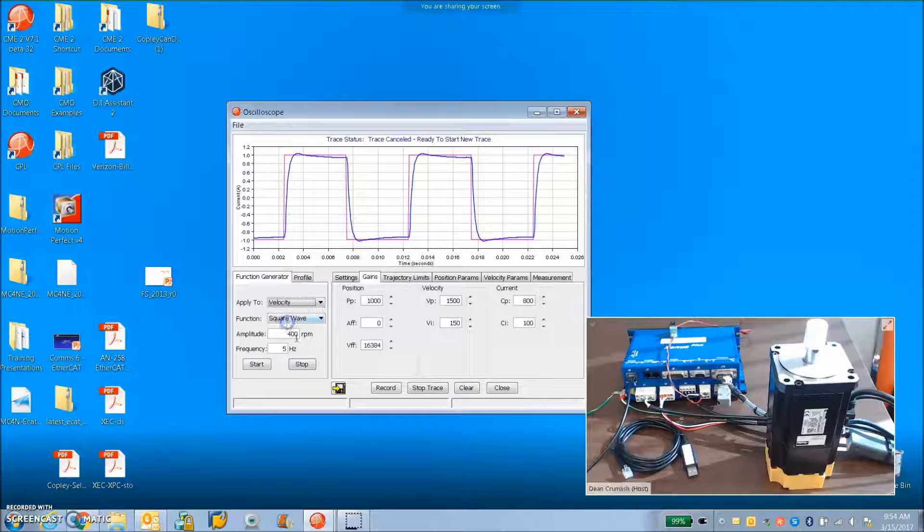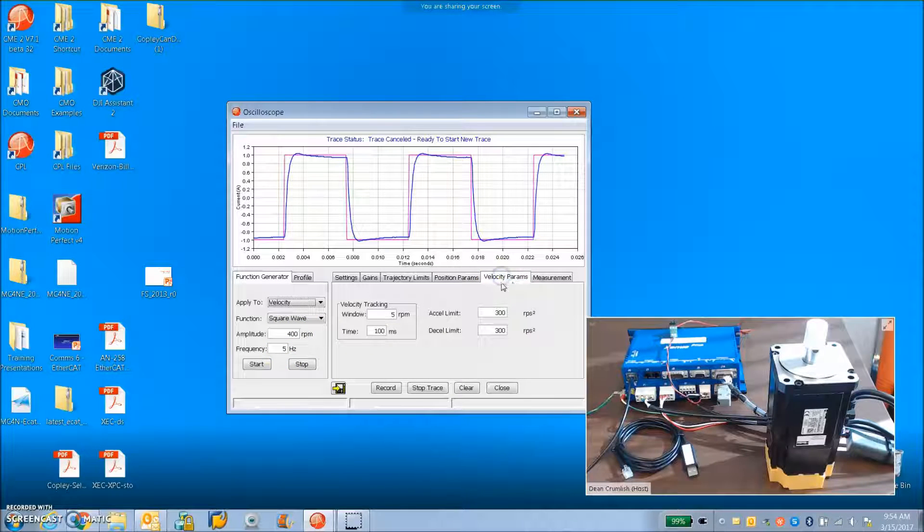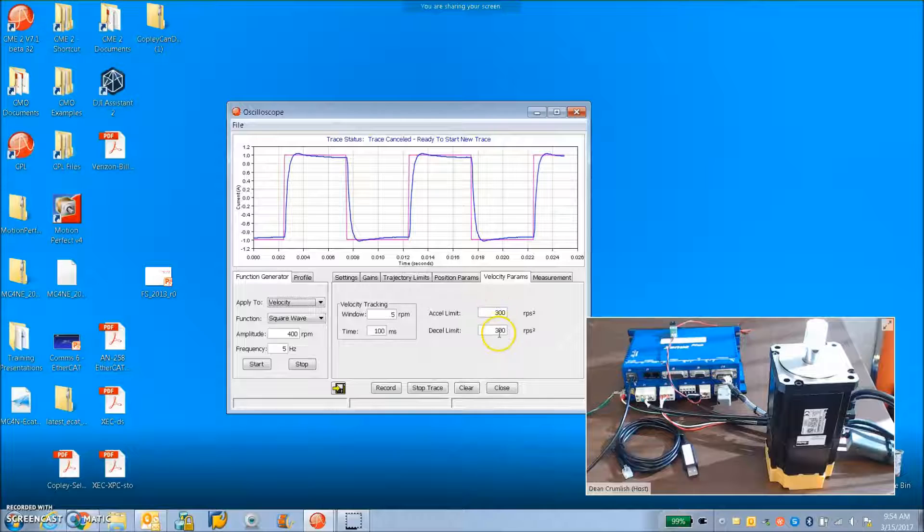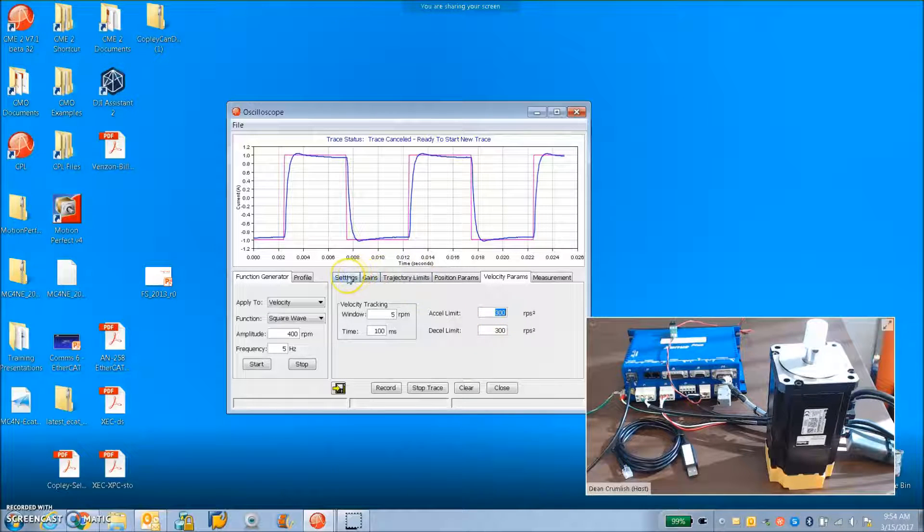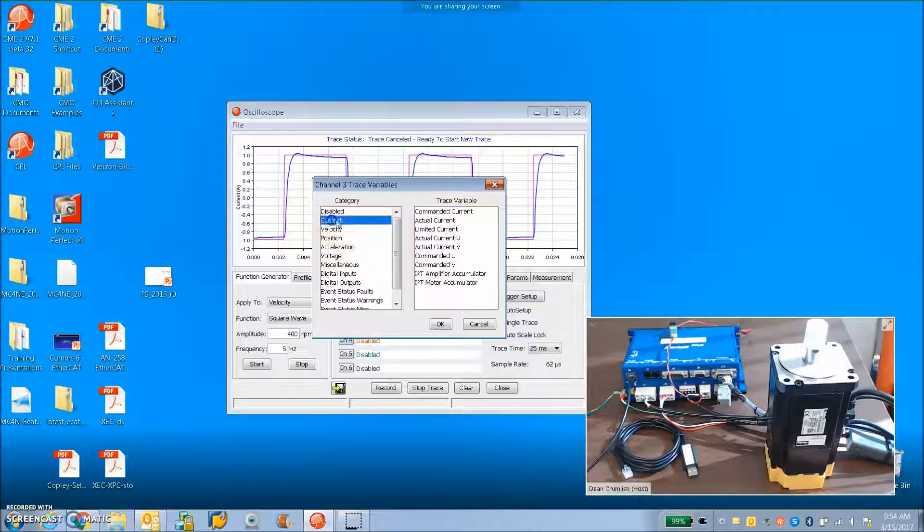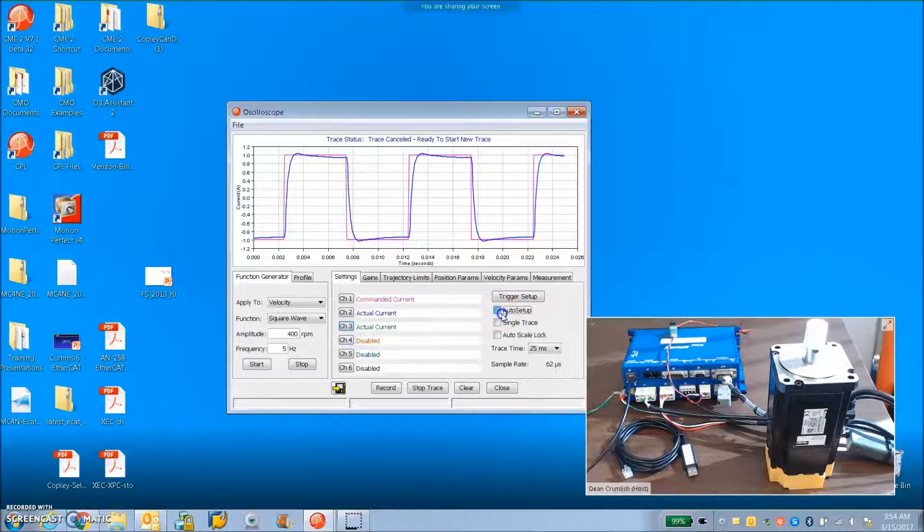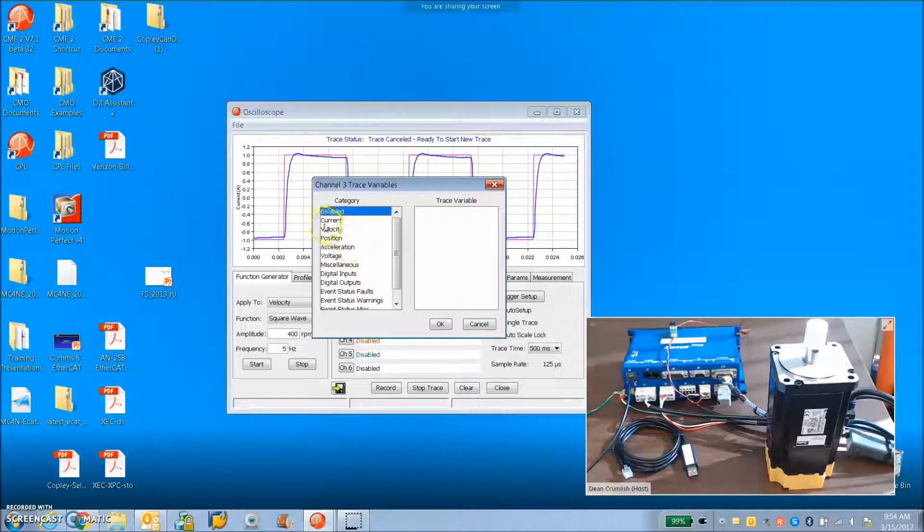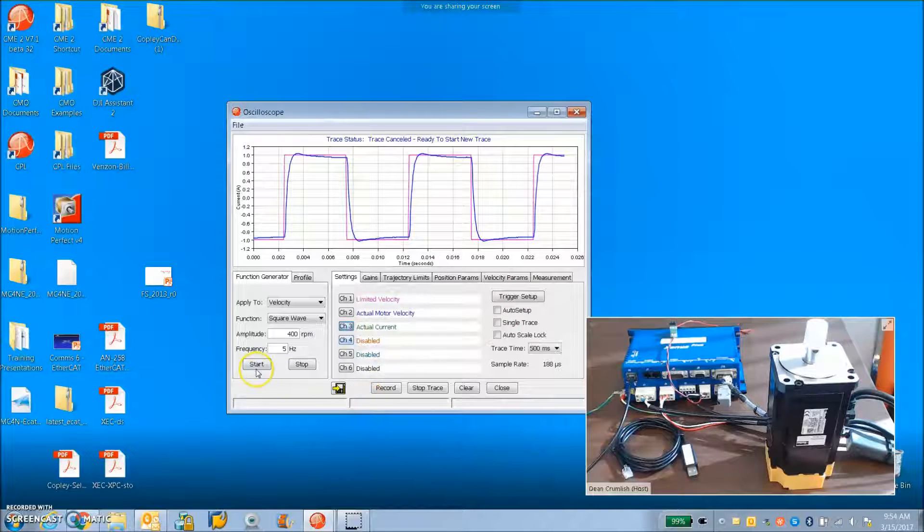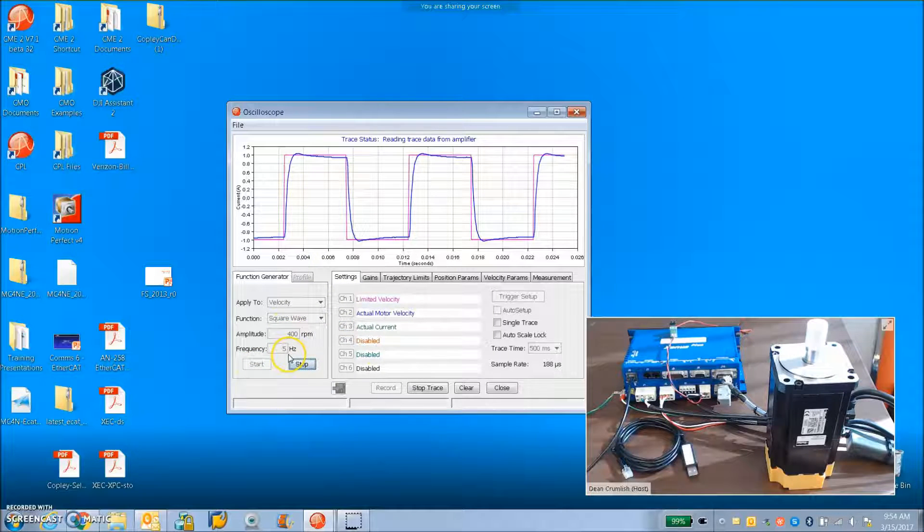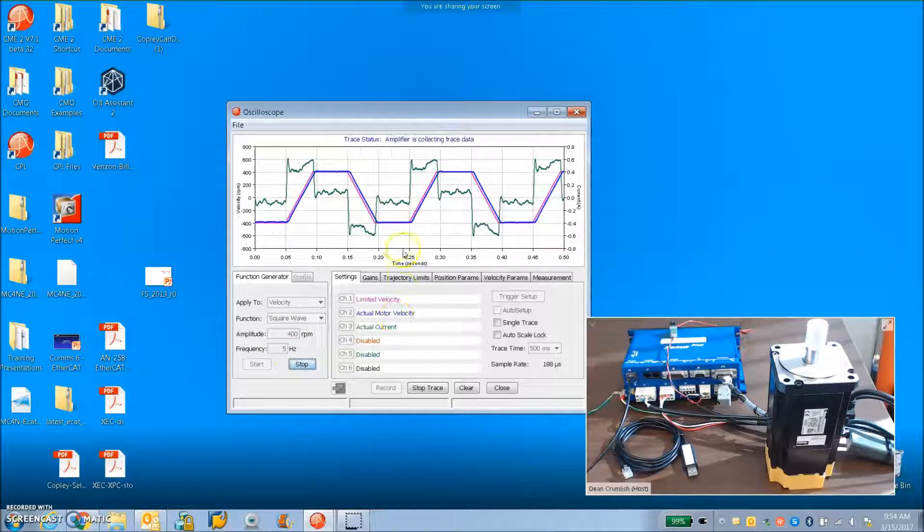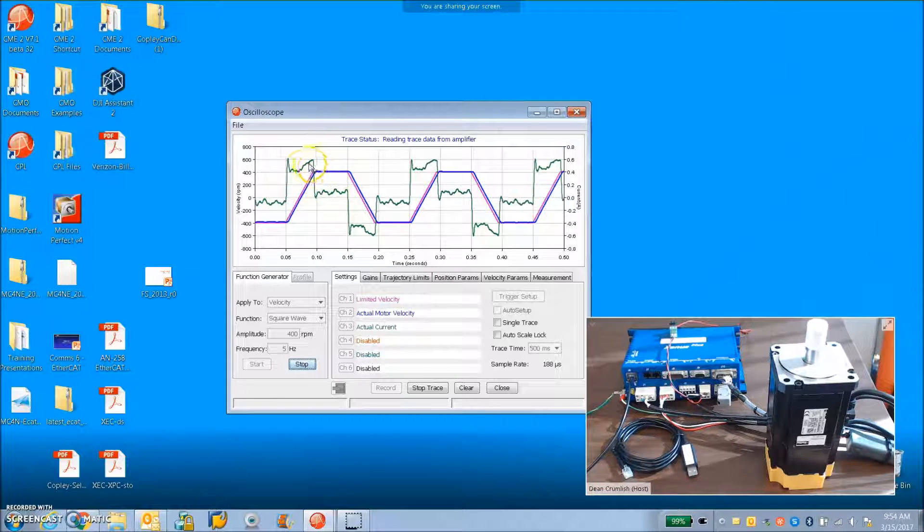For the velocity loop, 400 RPM, 5 hertz is fine. But on the velocity parameters tab, you want to knock the acceleration down to 300 revs per second for accel and decel. And I like to look at the current actual along with the auto setup checkbox. Current, actual current. And we can hit start on this. Back and forth, hits 400 RPM, 5 hertz. This is a no load test. A little bit of current for accel. My tuning looks pretty good here.